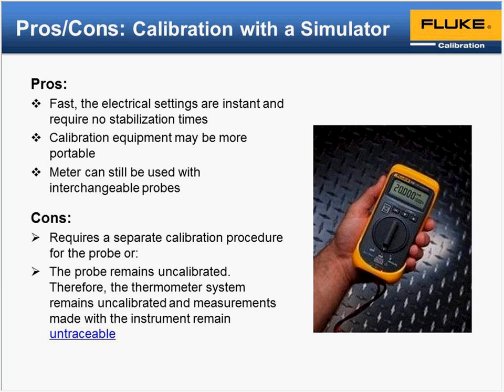Some of the cons though: we can't get everything in that simulation. We can't simulate both the probe and the readout together, so we've still got that unknown of the probe that was not addressed in the simulation calibration that we did on just the electronics. So in our case, for argument, the calibration that we perform would not be considered traceable, because of that missing piece on the probe side.